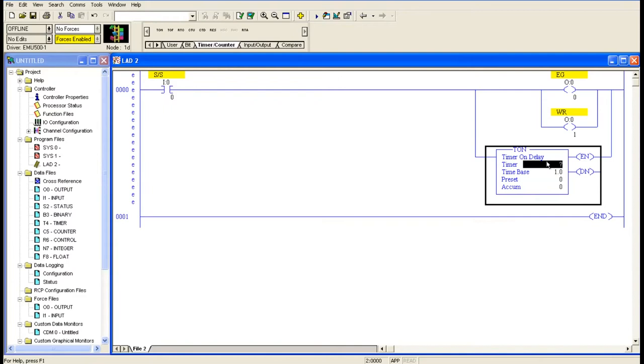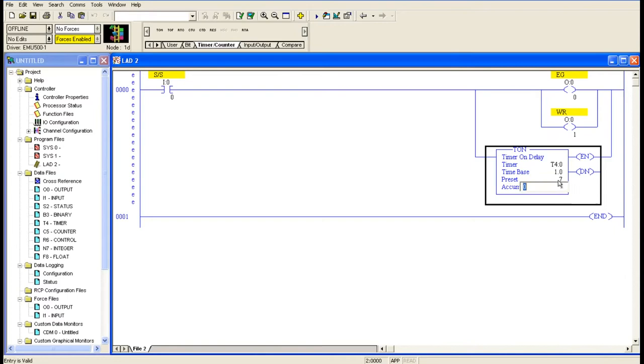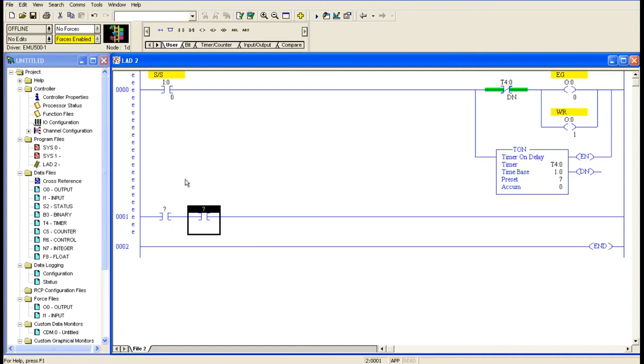This timer is T4:0 and I'll give it a 7-second delay. After 7 seconds both outputs should go off, so I'm putting one normally closed contact as common to east green and west red — that is the timer's done bit, T4:0/DN. The second cycle: when the start switch remains on, after this time delay two outputs will turn on — east yellow and west yellow.